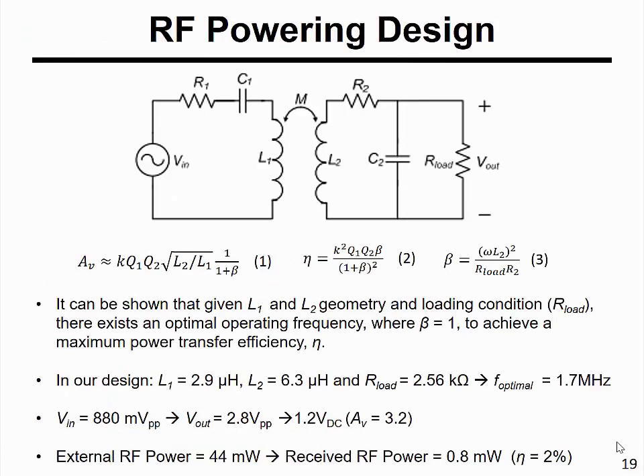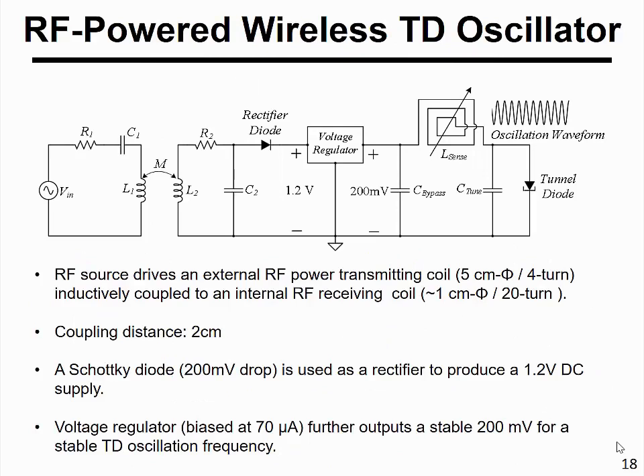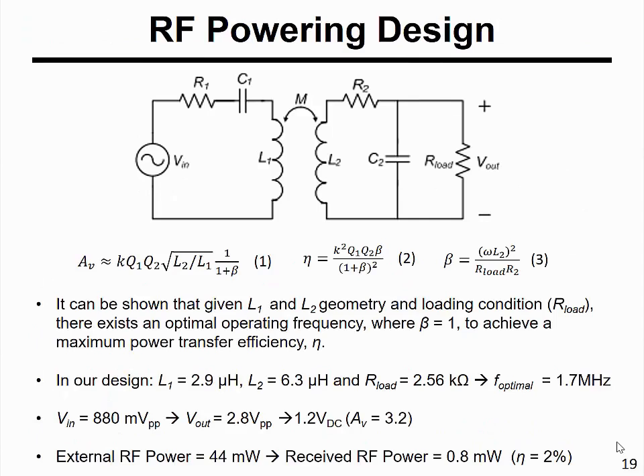So this is the RF powering design, where I have 3 equations. The first one is the voltage gain, the second one is the efficiency, and the third one is what we call beta, which is in the first 2 equations. So it can be shown that given the geometry I have shown and loading condition, there exists an optimum powering frequency where beta is equal to 1 to maximize the efficiency. And in our design, L1 is about 3 microhenry, L2 is about 6 microhenry, and this R load, 2.56 kilo ohm, is actually the equivalent AC resistance looking into this rectifier diode. And with these, we calculate the optimum frequency to be around 1.7 megahertz and a voltage gain about 3.2.